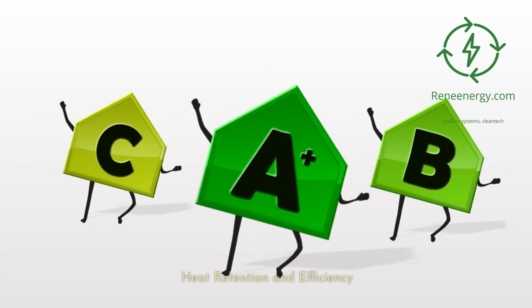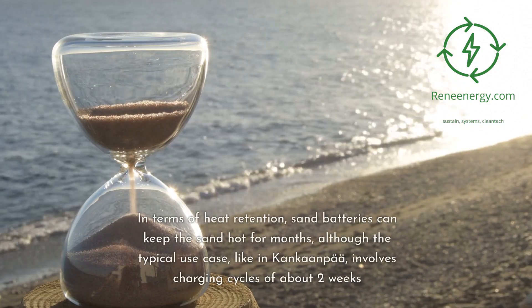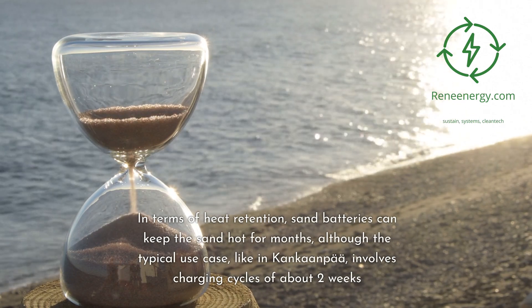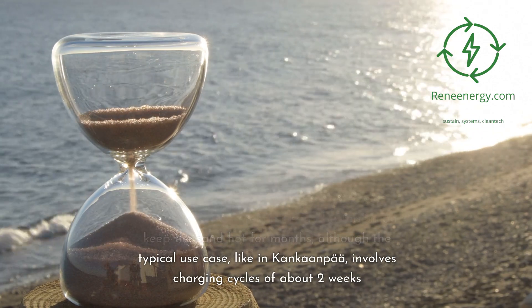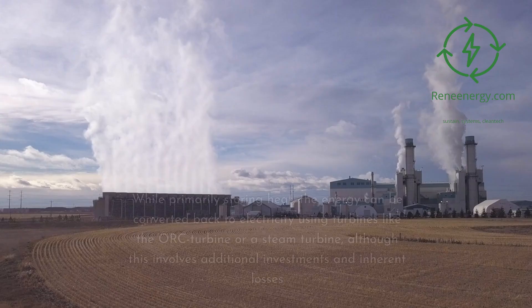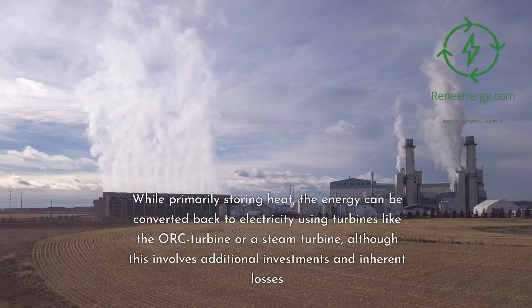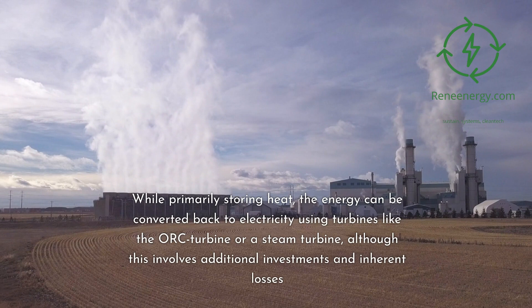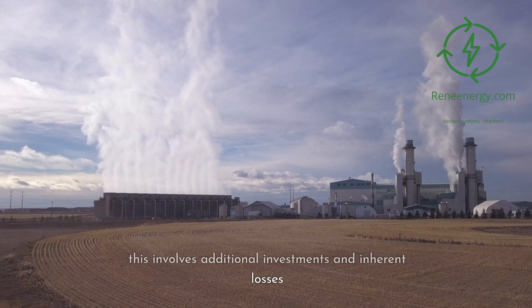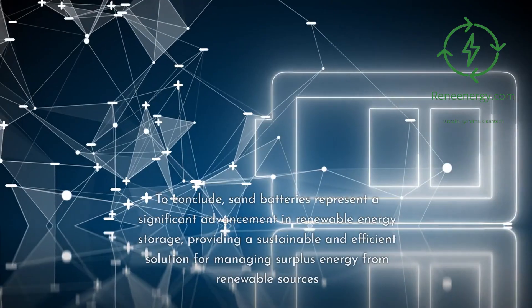Heat retention and efficiency: sand batteries can keep the sand hot for months, although the typical use case, like in Kankaanpää, involves charging cycles of about two weeks. These systems are most efficient when charged and discharged 20 to 200 times per year, depending on the application. While primarily storing heat, the energy can be converted back to electricity using turbines like the ORC turbine or a steam turbine, although this involves additional investments and inherent losses.